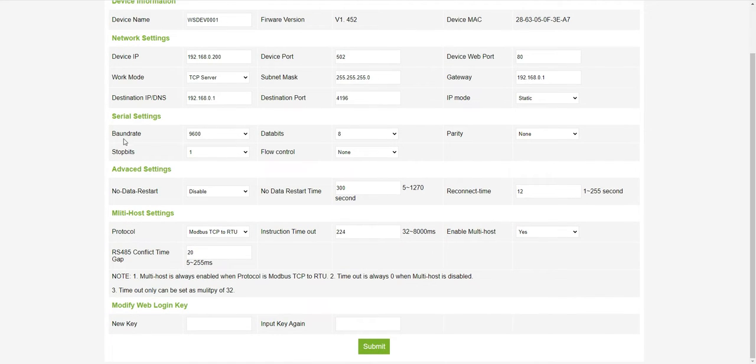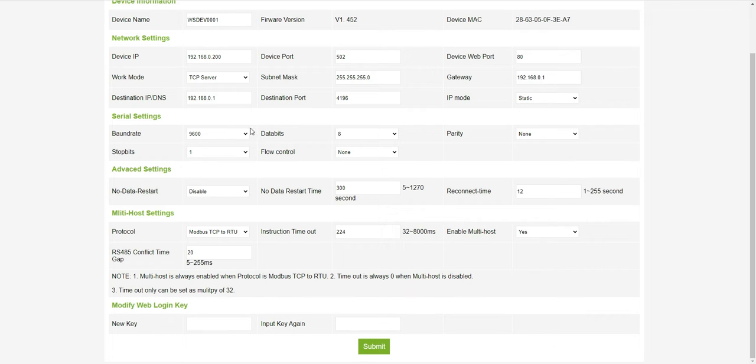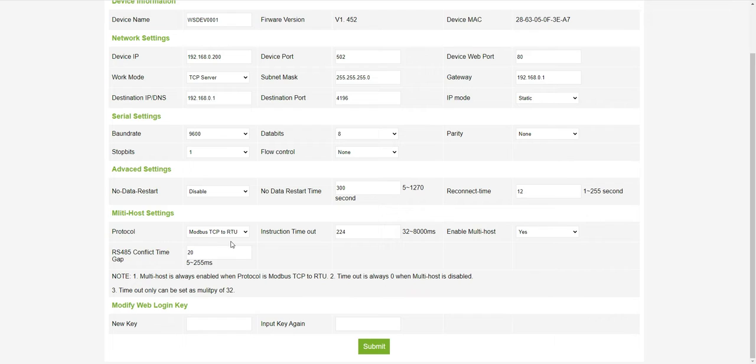So now we got the settings. Any device which you want to connect must have the settings. Basically, I will be using from the previous videos the temperature sensors and the electricity meter which have these settings. You must match these settings with the device which you want to connect. Protocol mode was TCP to RTU.